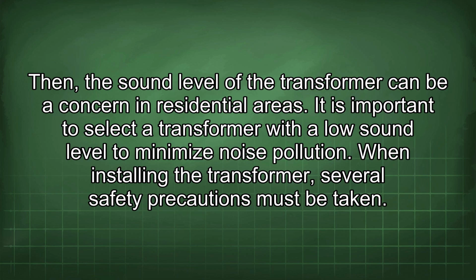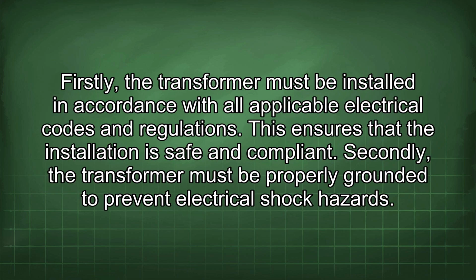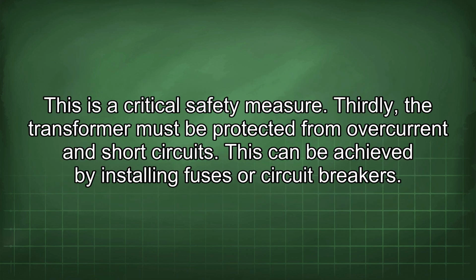When installing the transformer, several safety precautions must be taken. Firstly, the transformer must be installed in accordance with all applicable electrical codes and regulations. This ensures that the installation is safe and compliant. Secondly, the transformer must be properly grounded to prevent electrical shock hazards. This is a critical safety measure. Thirdly, the transformer must be protected from overcurrent and short circuits. This can be achieved by installing fuses or circuit breakers.